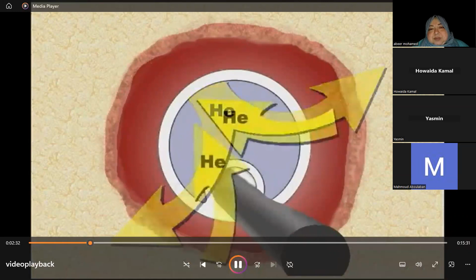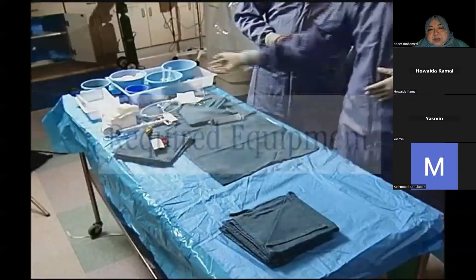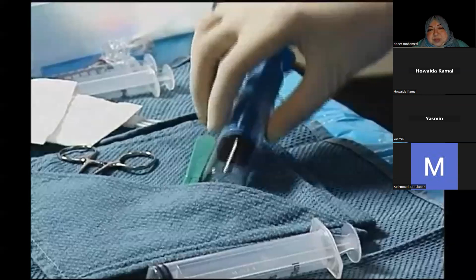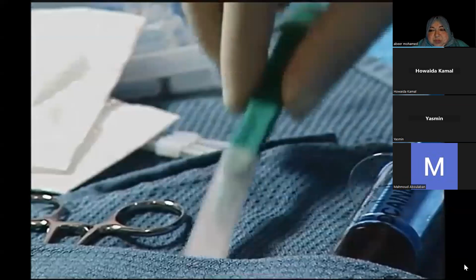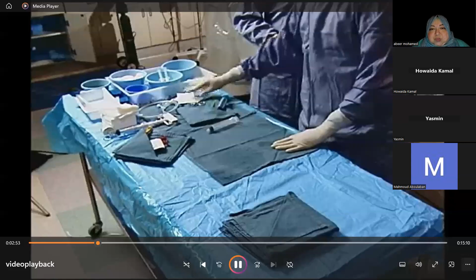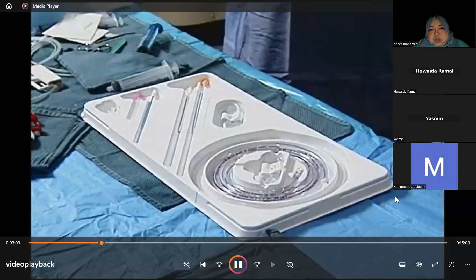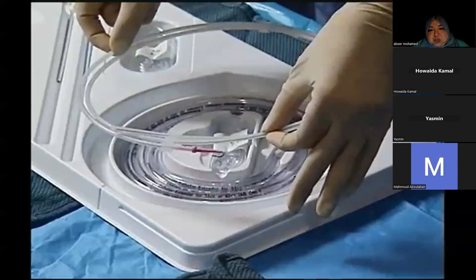To prepare for sheathless insertion of the intra-aortic balloon catheter, assemble the following sterile equipment: 1 basin of saline, local anesthetic with syringe and needle, 1 scalpel and blade, 1 20 cc syringe, lint-free sponges, 1 Kelly clamp or equivalent. Open the sterile insertion kit first. It contains all remaining required equipment for balloon insertion: 1 18-gauge angiographic needle, 1 J-tip guide wire, 1 tapered tissue dilator, 1 three-way stopcock, 1 male luer lock plug.